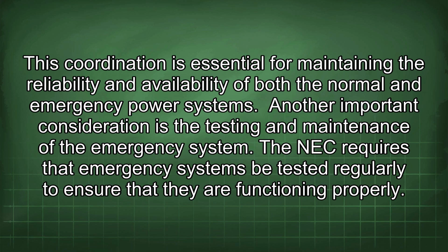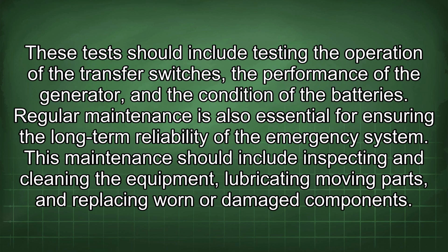Another important consideration is the testing and maintenance of the emergency system. The NEC requires that emergency systems be tested regularly to ensure that they are functioning properly. These tests should include testing the operation of the transfer switches, the performance of the generator, and the condition of the batteries. Regular maintenance is also essential for ensuring the long-term reliability of the emergency system. This maintenance should include inspecting and cleaning the equipment, lubricating moving parts, and replacing worn or damaged components.